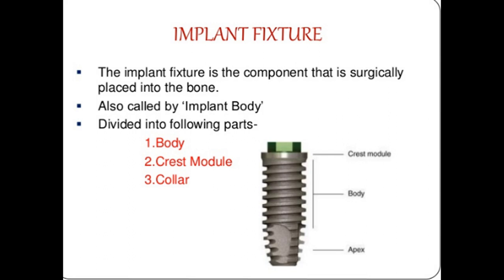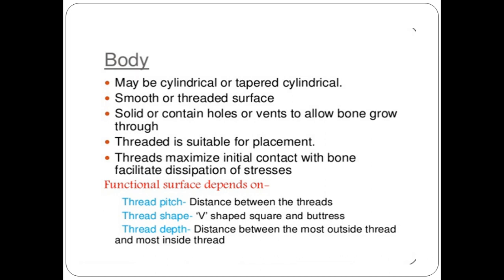The implant fixture is the main part of the implant placed in the bone — also called the implant body — and can be divided into the body, crest module, and collar. The body may be cylindrical or tapered, with a smooth or threaded surface, and may be solid or contain holes or vents to allow bone ingrowth. Threaded designs maximize initial contact with the bone and facilitate stress dissipation. Key thread parameters include thread pitch (the distance between threads), thread shape (V-shape, square, or buttress), and thread depth (distance between the outermost and innermost thread).